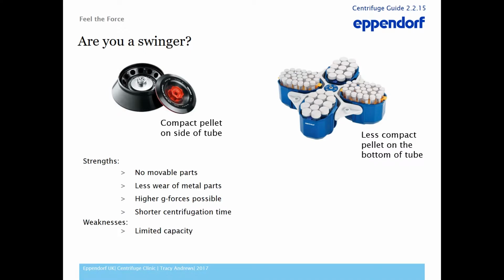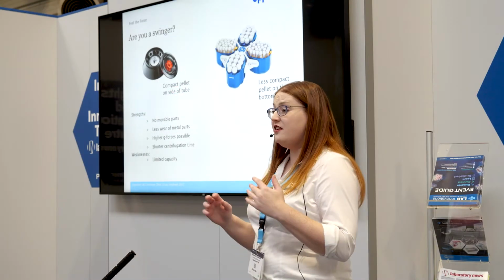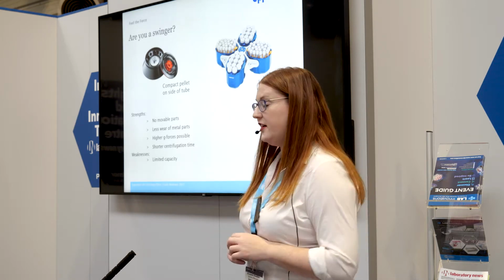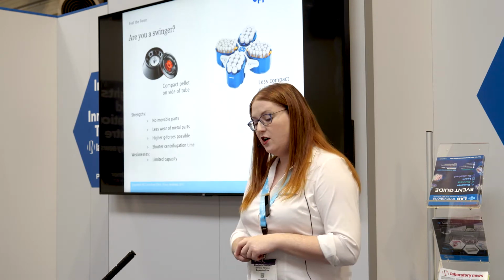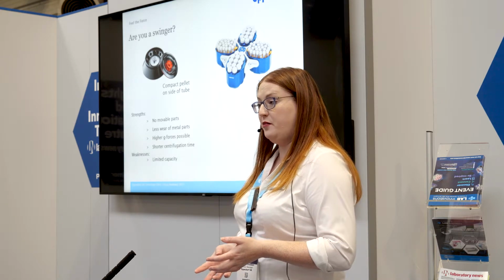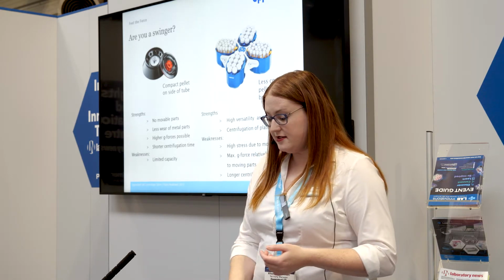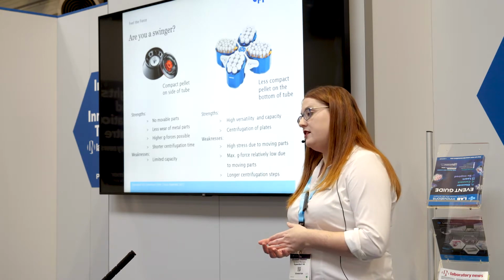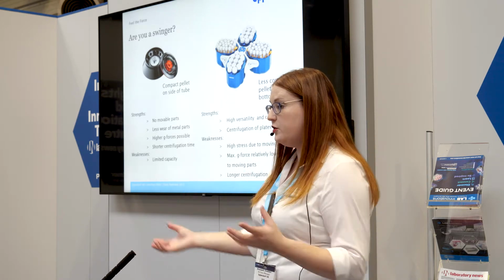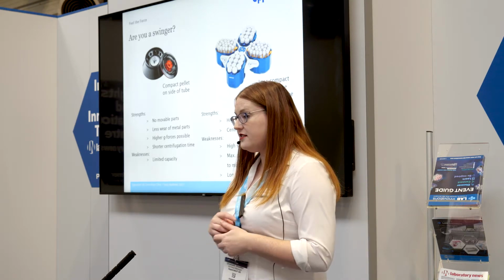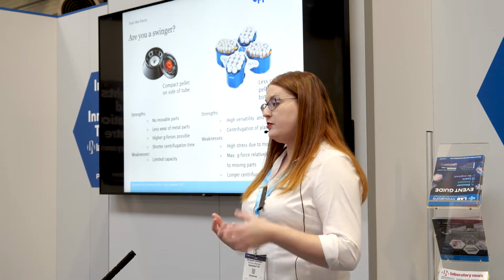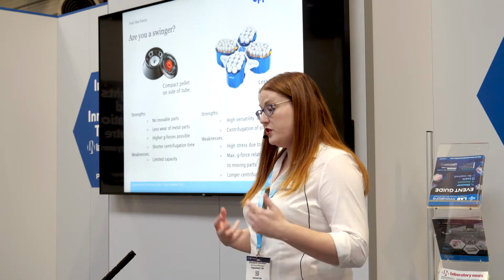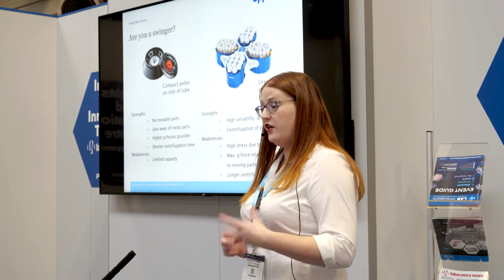So, fixed angle versus swing out rotors. There are strengths and weaknesses to both. So the strength of a fixed angle rotor is obviously that there are no moving parts, which means it can go much faster, which is great because you're going to get really, really compact pellets. Unfortunately, you are going to be limited on capacity. By comparison, the strength of the swing out rotor is you can be really versatile and have huge capacity. And you can do things like plates. But there's much more stress on the rotor because of all the moving parts, which means you have to run it a lot slower and often longer.